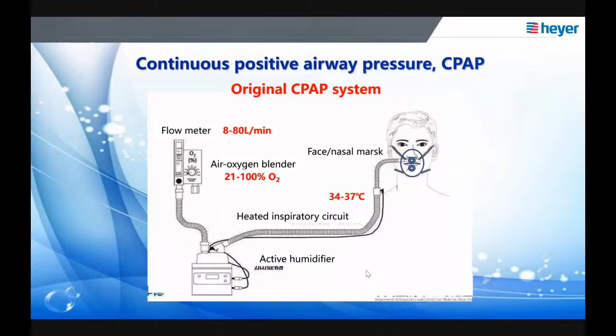There are two holes. This tubing comes from a high flow system. The flow rate we already know is 60 to 80 liters per minute. This is the PEEP valve. This PEEP valve can keep a resistance to expiration. So the key point is we need to give enough flow rate to keep the PEEP valve always open, that can keep the airway in positive pressure.